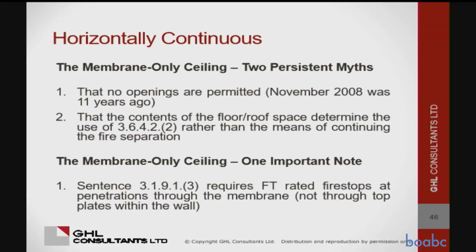So these myths, there's 2 sort of myths that we talk about all the time with this ceiling, and that is, 1, that no openings are permitted, which is what the code change fixed in 2008. And the other one is sort of getting mixed up about what's a horizontal service space in sentence 3.6.4.2.2. So that sentence says that you can butt your vertical fire separations up against this ceiling.